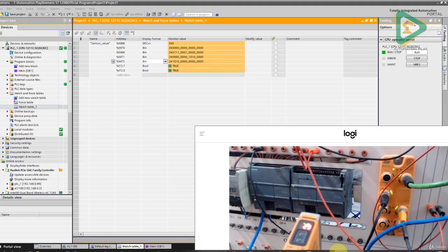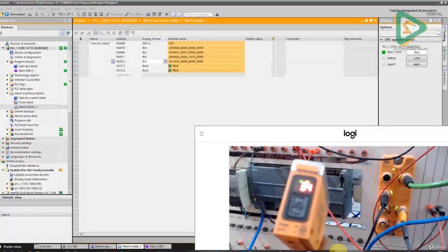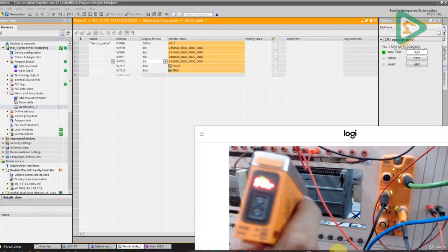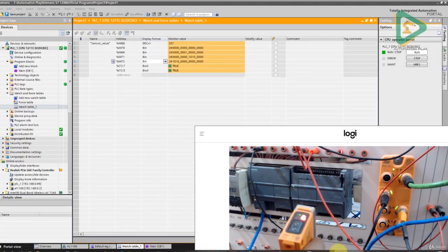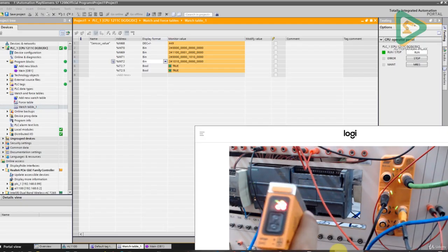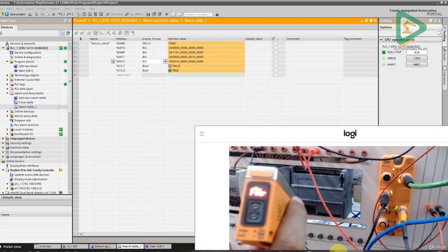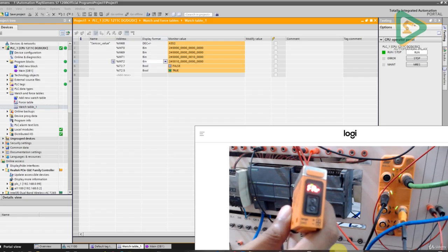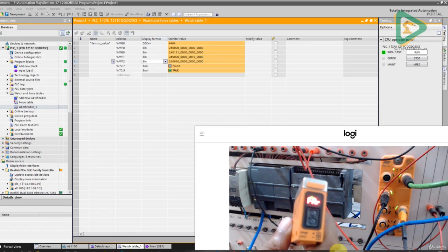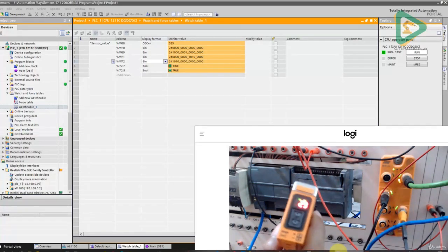And if it's in range like that, sorry, my I72.7 right now is false. If it comes in range, it's true. So you can use I72.7 for diagnostic purposes, and I72.5 is always true because it shows my sensor connectivity to IO link.